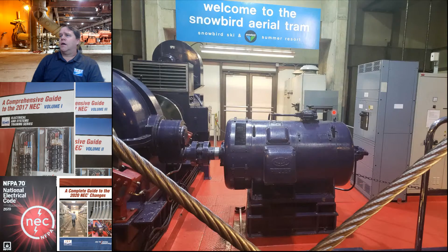Here you've got a massive VFD. Believe it or not, this is an auto transformer, because this is a 600 volt motor - not medium voltage, but actually a 600 volt DC motor if I'm not mistaken. So they bring in 480 volts, hit a buck boost auto transformer, kick it up to 600, convert it to DC, and that's how they run that DC motor.